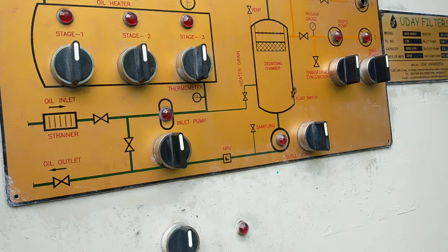Okay, and after evaporating those gases, the remaining oil will be passed on. Here you can see the sample valve. By this valve we can take an oil sample for BDV testing, like that. During filtration we cannot take an oil sample near the transformer, so we can take oil by this valve. From the outlet, oil will be entering into the transformer.